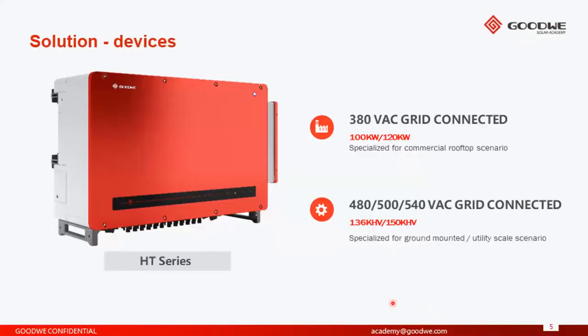Here, again, we will have two classes. The one class is with exit at 380 volt AC, typically the 100 and 120 kilowatt. And this will be still an extension of our MT series for a commercial rooftop or for small ground mounted project. And the two versions with exit at 480, 500 or 540 volt AC are the versions, let's say, specially designed for utility scale project.